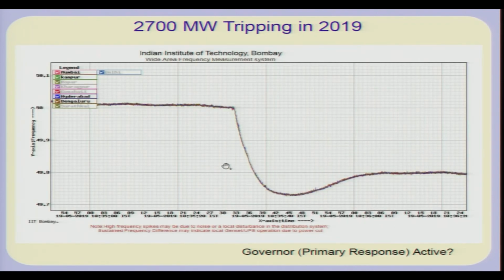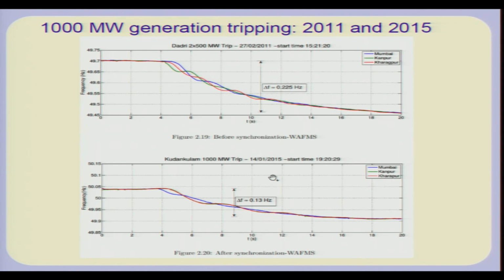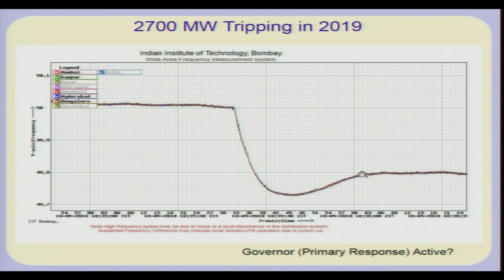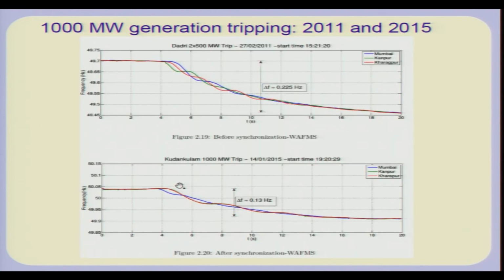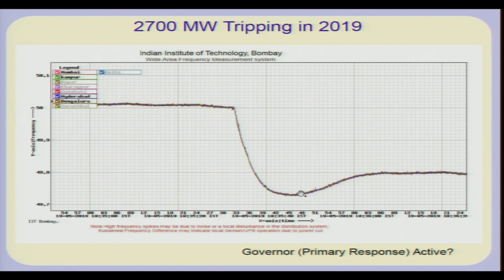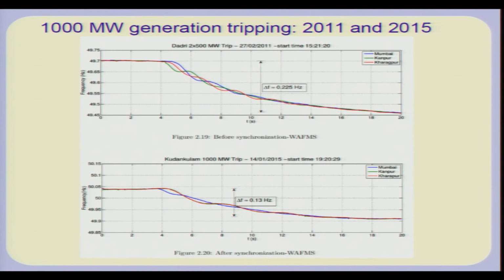In fact, most recently we find similar behavior, and one of the differences we see between 2015 and 2019 is that, whereas earlier it is more or less an exponential kind of drop, 1 minus e raised to minus t by tau, like an RL circuit, here you see a kind of second order response. This is probably because of control systems like governors, which are now more active. In 2011 not all governing systems were active, but the new grid code in fact requires governors to be active. So, you see a second order response, slightly different from the plain e raised to minus t by tau kind of response.